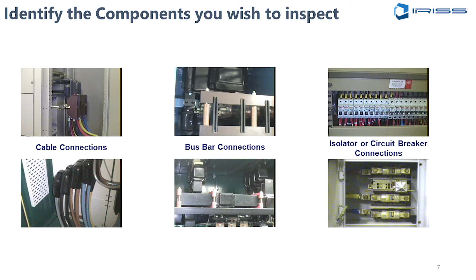How long will it take to become a significant issue? That's always the question. So any point where we're transitioning, any semi-permanent connection between two conductors, is something we want to inspect, because it can become a thermal issue, and those thermal issues can easily become ultrasound-based issues too, giving off partial discharges. So that's what we want to look at.